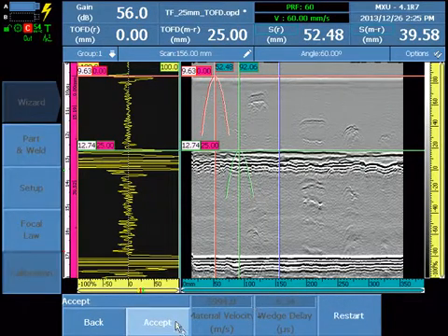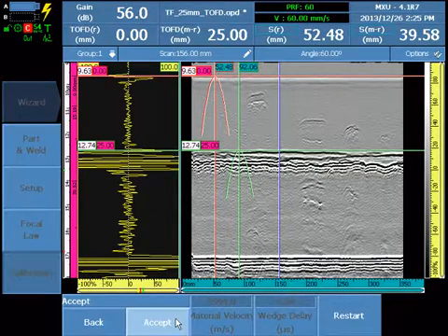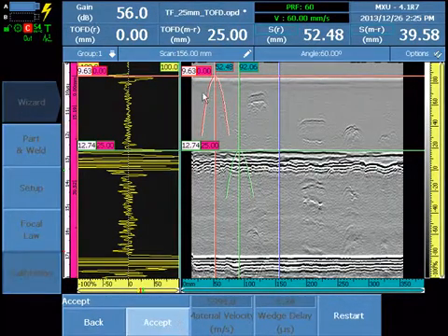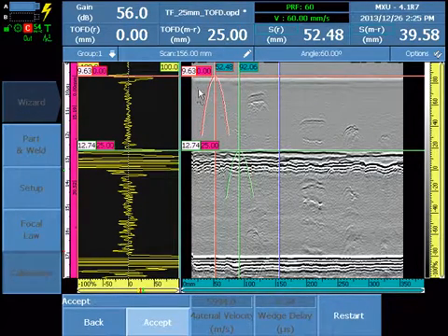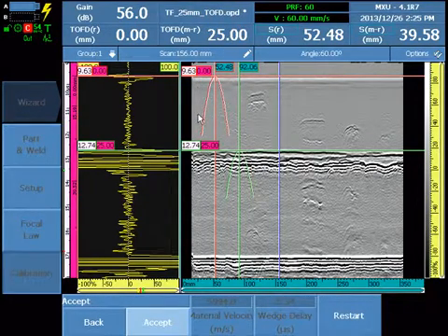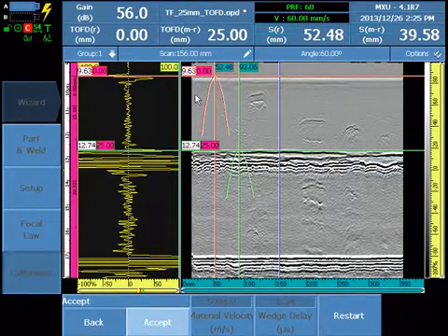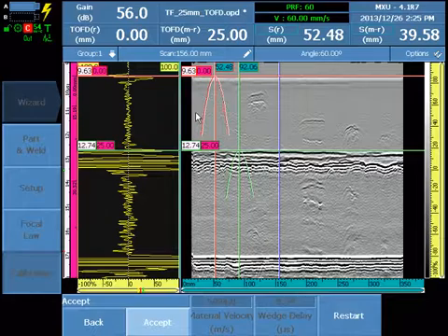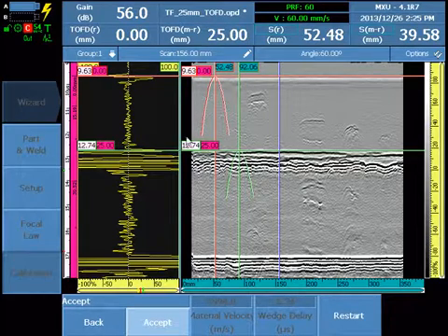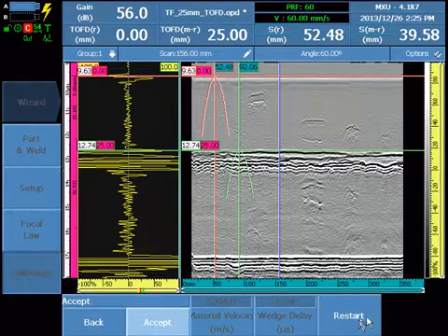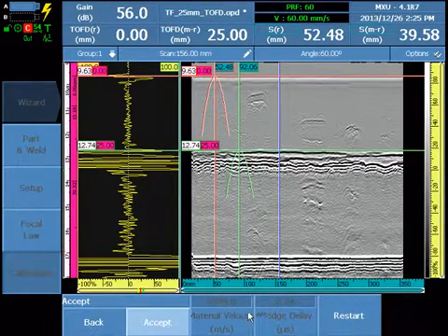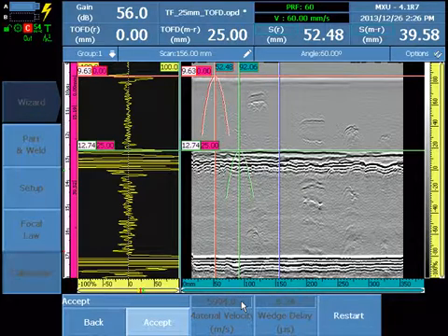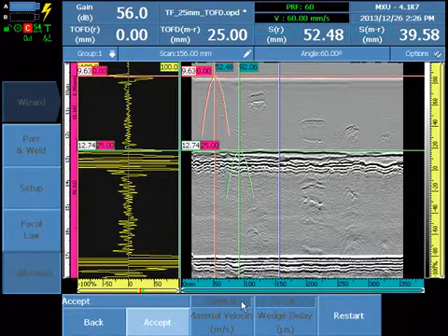Acceptance of this will linearize the UT axis and measurements will be possible in between the cursor areas. Selecting restart again clears the new calculated velocity and will revert back to the original one, which is recommended under most conditions.